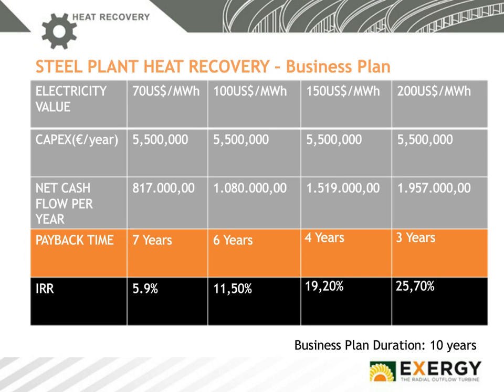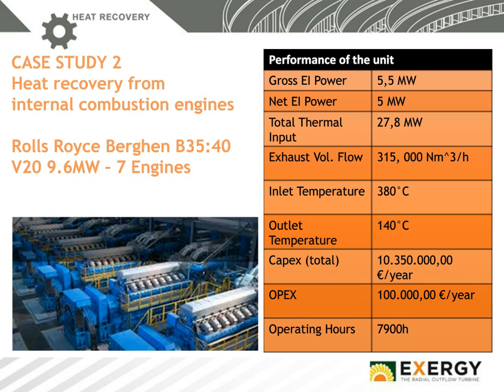The second case is the heat recovery from internal combustion engines. In this case, we are talking about 7 Rolls-Royce engines producing about 9.6 megawatt, and from these engines we can recover a total of about 5 megawatt net. So in this case, we are not talking about saving energy for the industrial production, but about increasing the efficiency of the system. In all the cases in which power is produced in open cycle, with an internal combustion engine or a gas turbine without a heat recovery system, the application of an ORC module can really increase the efficiency and thus reduce the cost of production of electricity.